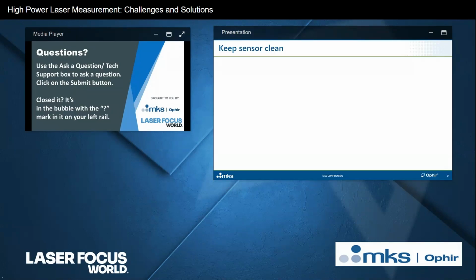Particularly when we're talking about the sort of high-power industrial applications where there's a lot of process debris flying around, and that could settle onto the sensor's absorber surface. So as they say, a milliwatt of prevention is worth a kilowatt of repair, or something like that. So if you get such process debris splashed onto your sensor, clean it off. Usually a soft tissue with a suitable cleaning agent.